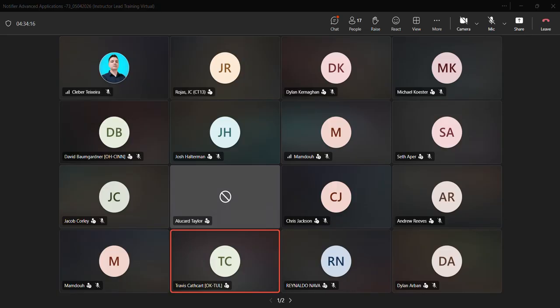Can you use X zone as a way to detect any 2 of the 5 pull stations? Yes. Well, X zone requires at least 2. So 2 or 3 or 4. If I'm not mistaken, you just put all 5 of the pull stations in one zone and then use X zone, and that works. It doesn't have to be the any 2 function, correct? Correct. Keep in mind the any two is strictly any two. The X zone, you need at least 2. So 3, 4 will activate that as well. Okay.